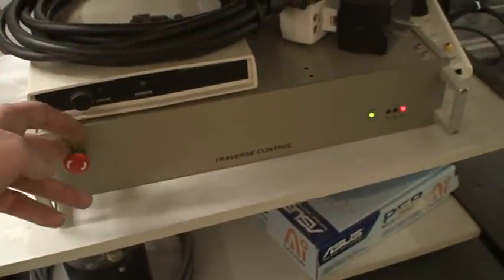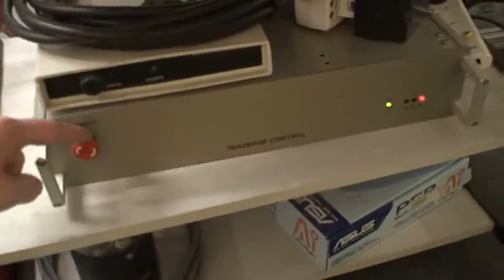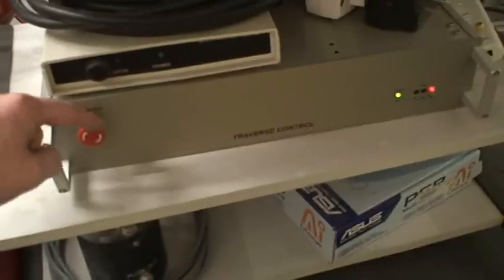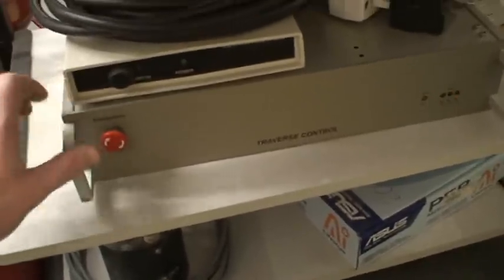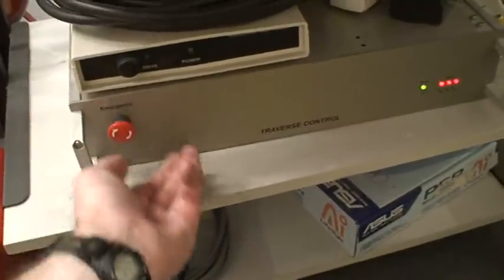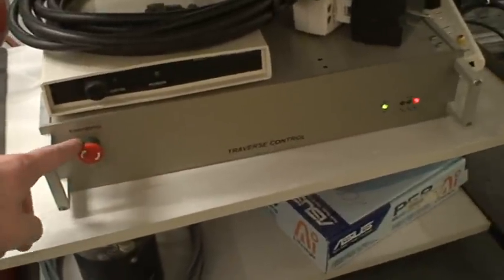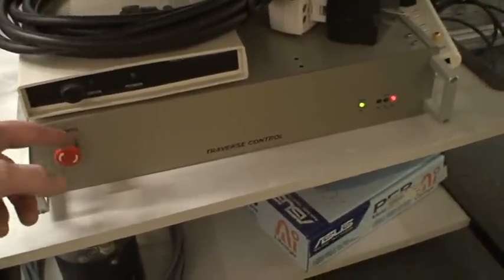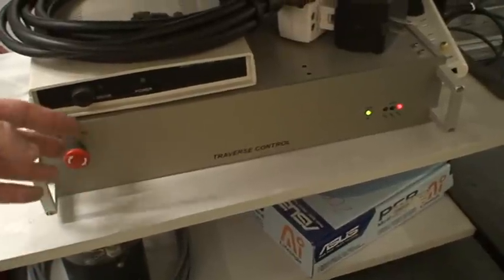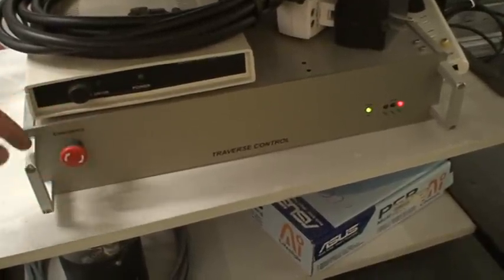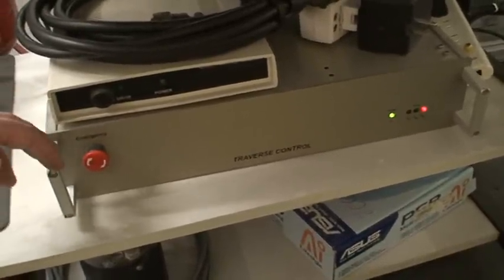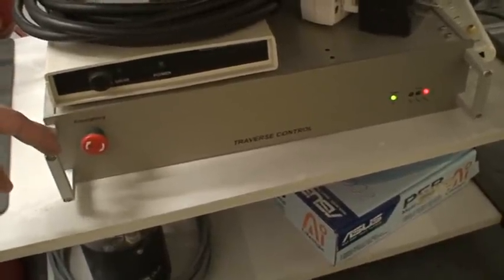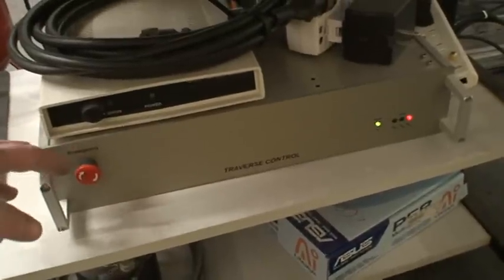It's important to note that if you turn it back on, it will continue to move the way it was set before. Or if you just release the emergency switch, you push it in—the unit will go off. If you rotate it, it'll come back on and it'll go back to moving wherever it was before. So you need to remove the obstacle or turn the entire unit off and back on, and then it'll just sit still.